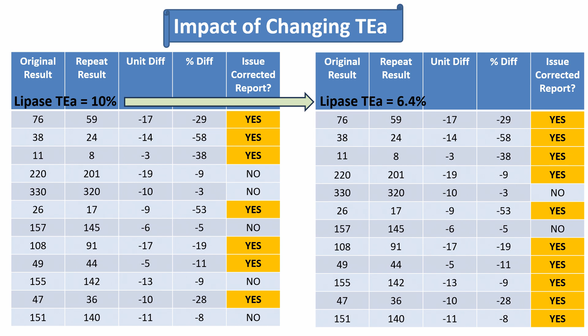Here we see for desirable, the total error goal is 12.9%, and optimal is 6.4%. I considered how lipase is used in my laboratory, the clinical utility, and decided to choose the midpoint, which is 10%. That's how I figured out what to put in this tool to tell techs whether or not to issue corrected reports. Now, if I wanted to switch to the optimal of 6.4%, so my quality specification or allowable error limit has changed, that will impact the number of corrected reports they need to issue for the same amount of difference when we repeat the QC after we've corrected the problem. So changing the allowable error limits changes the impact on the activity that you're applying it to.